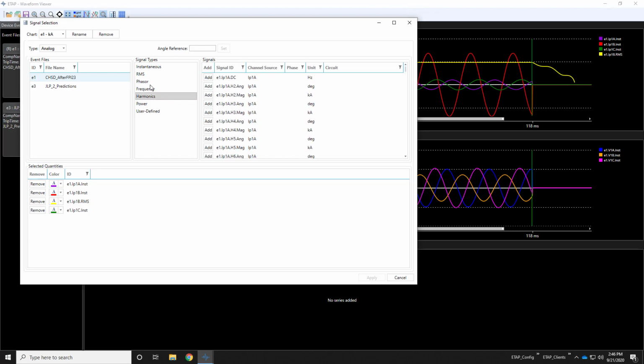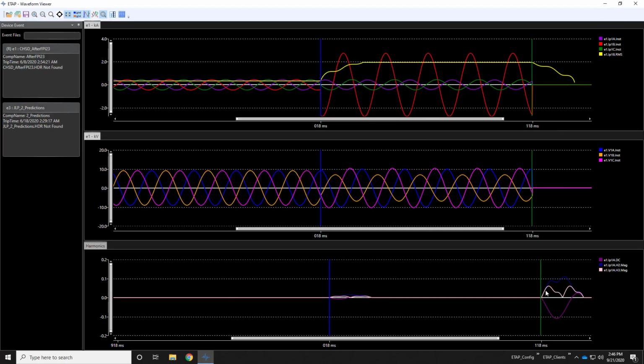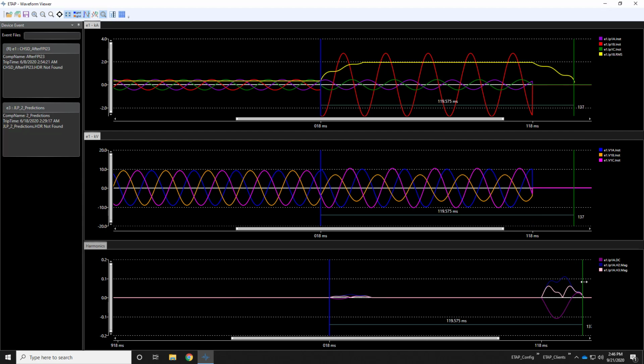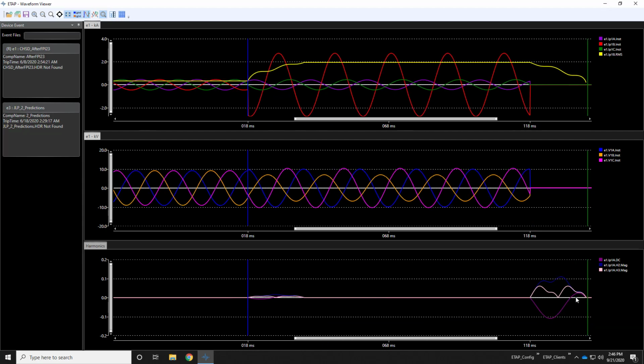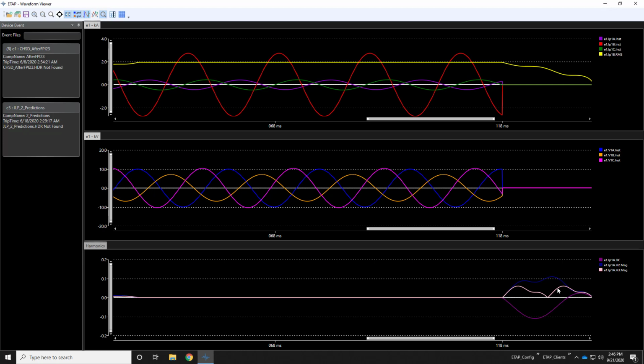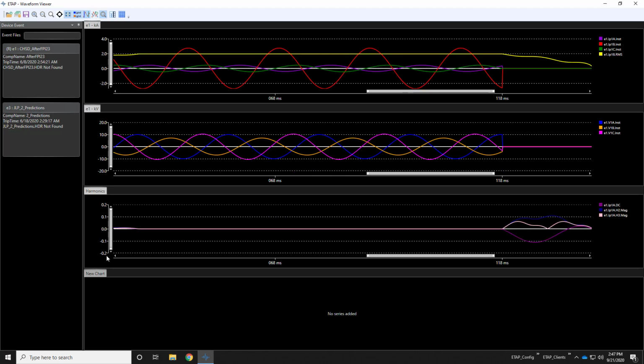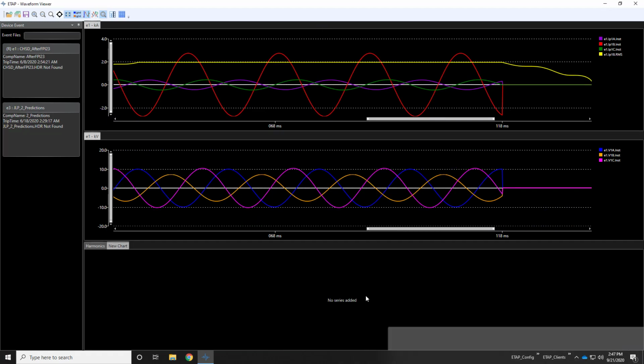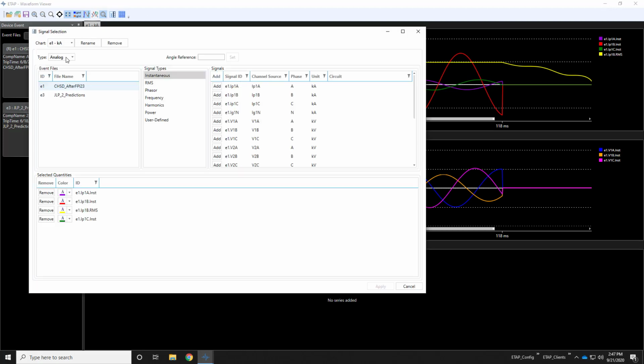I'm going to bring in my harmonics here to my harmonics page, and just bring in my DC, second and third order harmonics and apply those. And here we can see my harmonics data. So I can zoom in and see that this is where the harmonics information is available. Additionally, we can add new trends. So I'm going to add a new view, and I'm going to put it right here, and I'm going to populate it with power data.